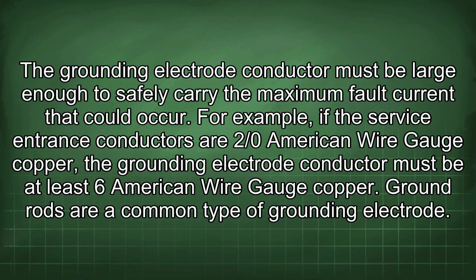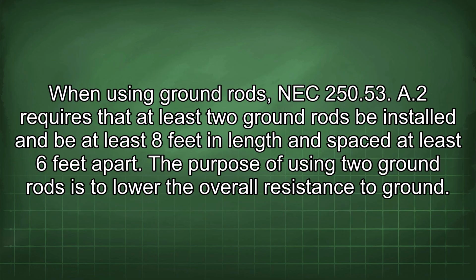Ground rods are a common type of grounding electrode. When using ground rods, NEC 250.53 A2 requires that at least 2 ground rods be installed and be at least 8 feet in length and spaced at least 6 feet apart. The purpose of using 2 ground rods is to lower the overall resistance to ground.